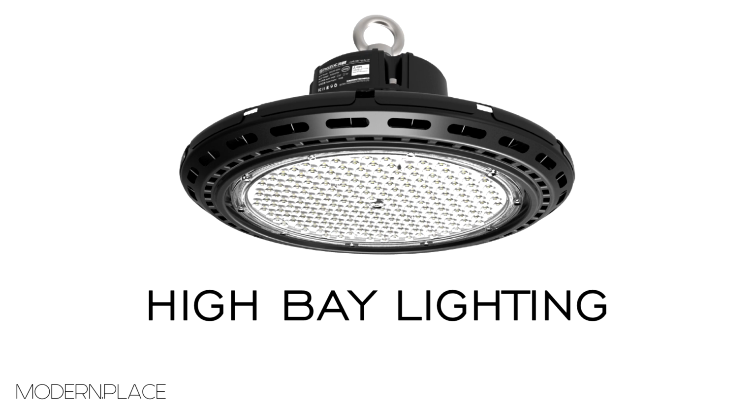So, for example, the LEDs inside of our UFO lights are Philips Lumileds 3030 2Ds, which at 5000 Kelvin are going to be around 163 lumens per watt. That's never going to be what you're actually getting when the light fixture is installed and operating together with the driver. Those specs are listed as the most optimal specs possible. They're tested for 20 milliseconds in the factory, and that's essentially how they're binned. So when you're looking at those specs, it might seem like, oh my god, this is so efficient.